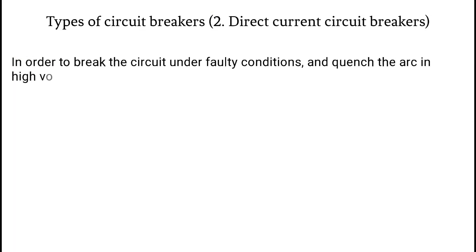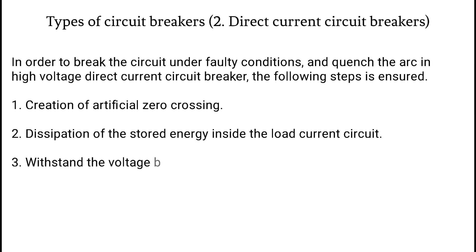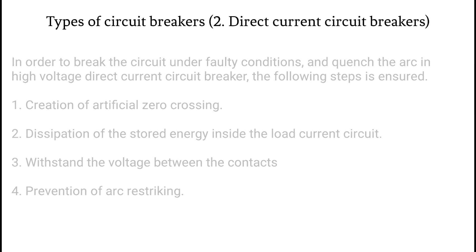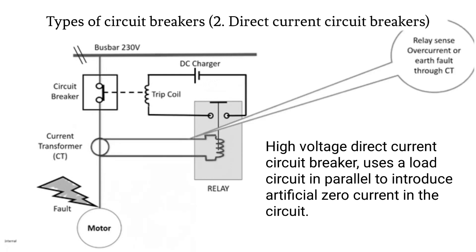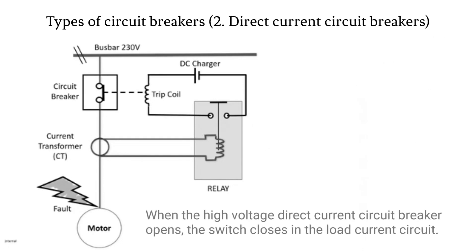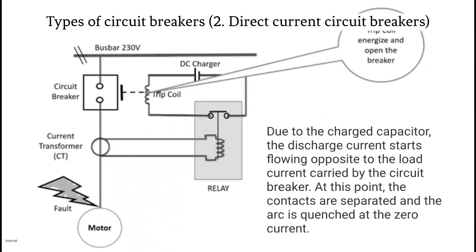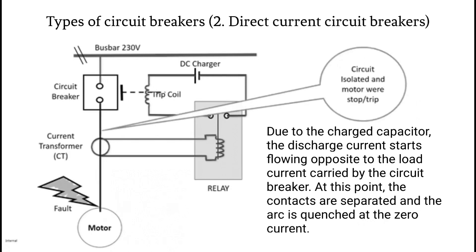In order to break the circuit under faulty conditions and quench the arc in a high voltage direct current circuit breaker, the following steps are ensured: 1. Creation of artificial zero crossing. 2. Dissipation of the stored energy inside the load current circuit. 3. Withstand the voltage between the contacts. 4. Prevention of arc restriking. High voltage direct current circuit breaker uses a load circuit in parallel to introduce artificial zero current in the circuit. When the HVDC circuit breaker opens, the switch closes in the load current circuit. Due to the charged capacitor, the discharge current starts flowing opposite to the load current carried by the circuit breaker. At this point, the contacts are separated and the arc is quenched at zero current.